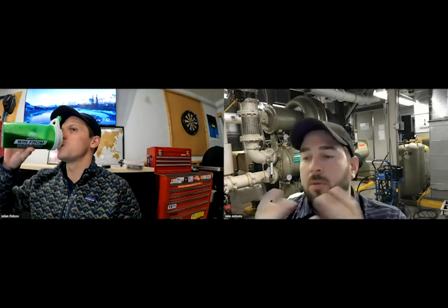If it's in an awkward spot or you're not able to do that, obviously you've got to remove the refrigerant, pull the valve out, replace it, and then pressure test, as we're going to be talking about shortly, and add the refrigerant back. There's definitely been lots of times where I've swapped out components at a low psi live.